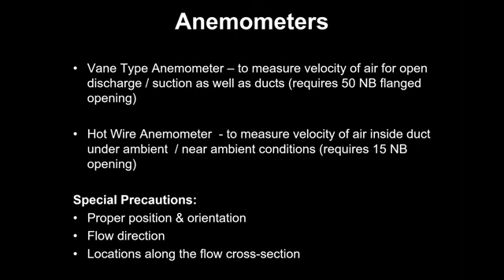Now, a hot wire anemometer has either one or two sensors. It will inject current in that heating element. As the air is flowing over that sensor, it is going to carry the heat. So, based on the temperature, you have one reference temperature. For that, there is a sensor which will sense the actual temperature, and another will be the temperature of the heated element. The temperature of the heated element will depend on the flow of air. That way it will measure the velocity and tell you what is the velocity of the air flowing over the anemometer. Also temperature, because another sensor is anyway there to measure the temperature. So you will get both the values. You will get temperature and velocity both, whereas a vane type anemometer will give you only velocity.